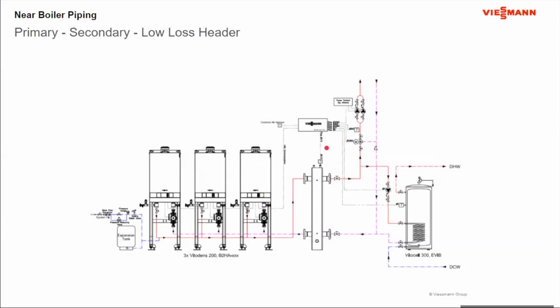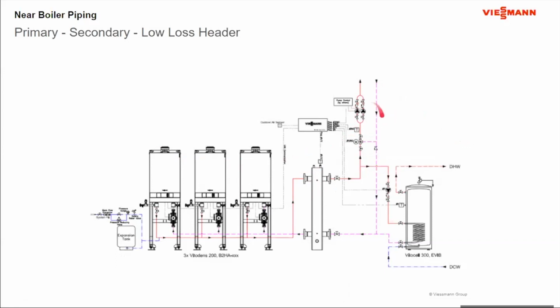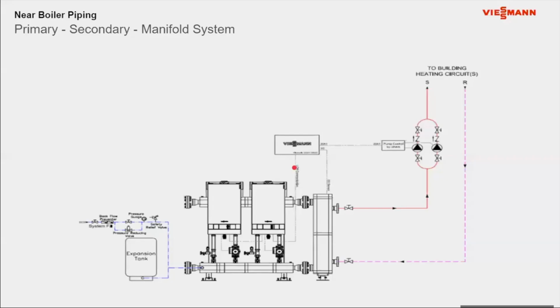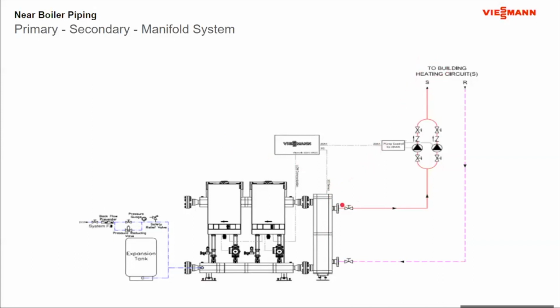As we said earlier, hydraulic separation, primary, secondary, is required with the wall-hung boilers. So here's a rack of 3 boilers. Here's my hydraulic separator, my low loss header, and then here's my connection out into the system. This can be done by individual boilers, individually mounted. Oh, we talked about a manifold system. So here it's shown on the manifold system as well. But manifold system, low loss header, and then out to the building, okay? But when we start to do primary, secondary, you notice this primary, secondary pretty much is applicable to every boiler out there. It's just a matter of how you want to achieve it.